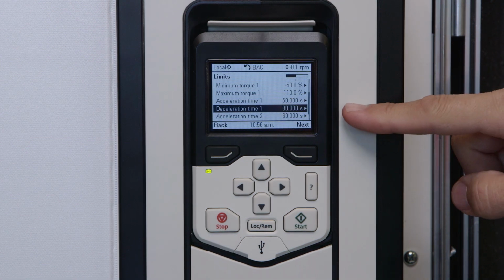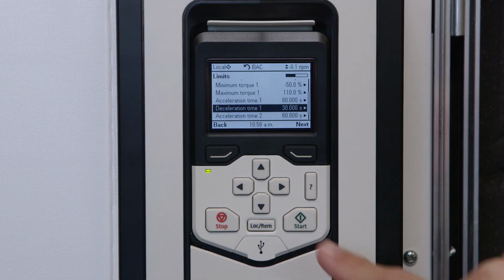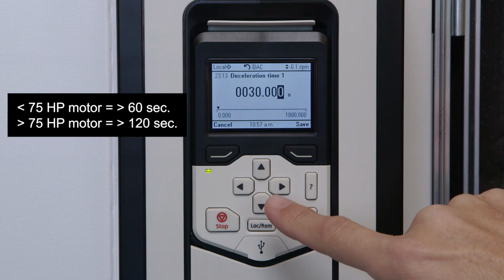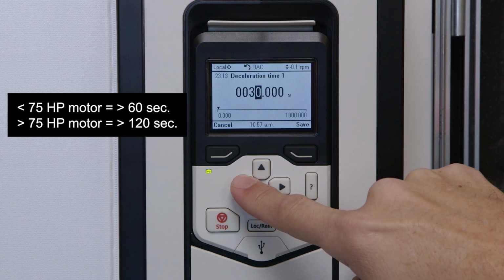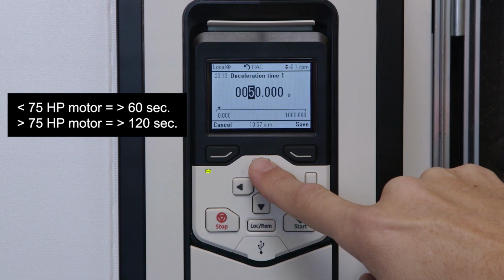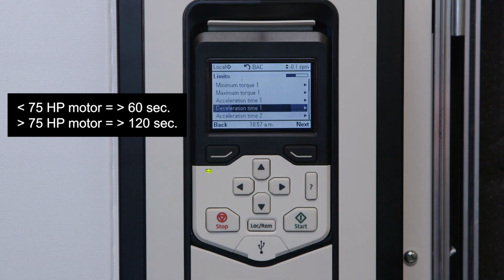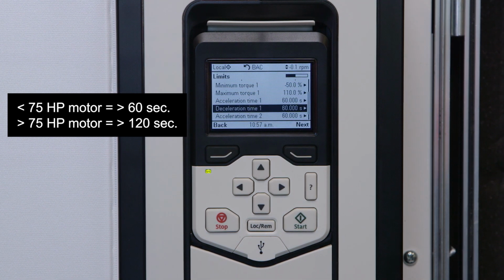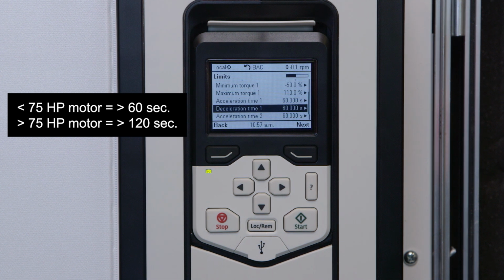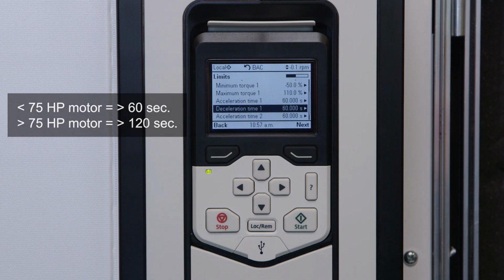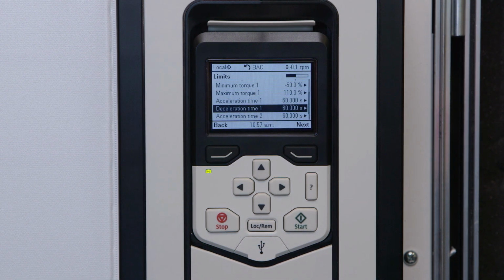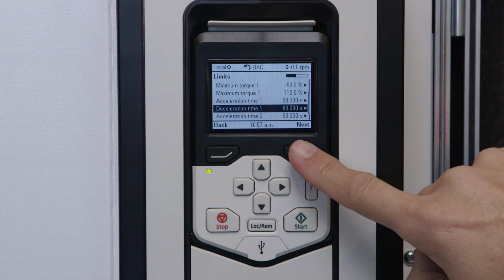As with acceleration, a longer deceleration time means slower ramping down, and a shorter time means faster deceleration. If the motor is less than 75 horsepower, the deceleration time should be more than 60 seconds. If the motor is more than 75 horsepower, the deceleration time should be more than 120 seconds. When values for both acceleration and deceleration are entered, press Next.